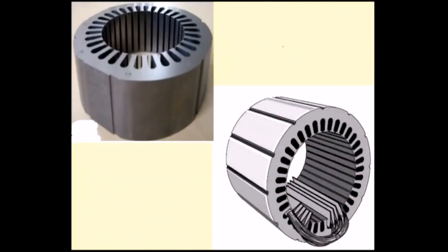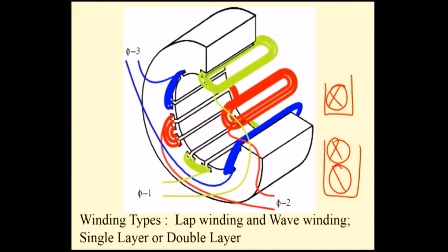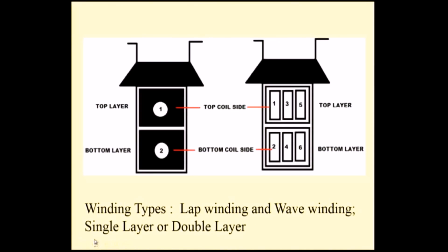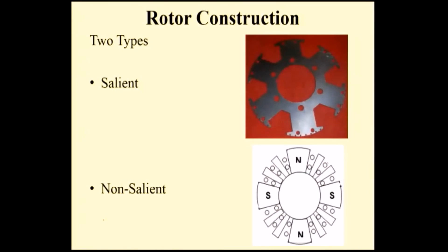The stator is not made of a single solid metal — it is made up of a number of stampings. The thickness of the stack is the core length, which is a design parameter. All the stampings are arranged according to the required core length, and though it looks like a solid piece, it is not. The inner periphery has a number of slots containing the armature winding. The winding may be single-layer winding — with only one layer per slot — or double-layer winding, with a lower layer and an upper layer. Three-phase winding is placed in this manner.